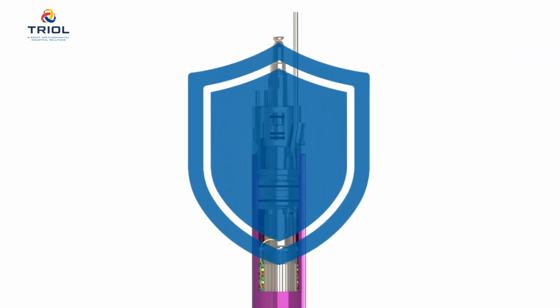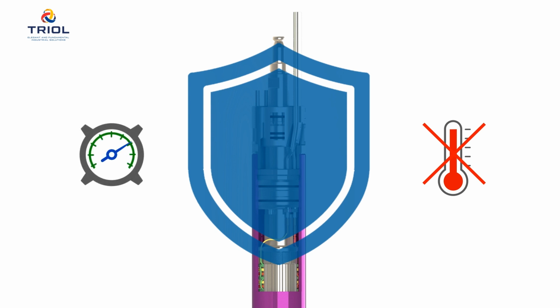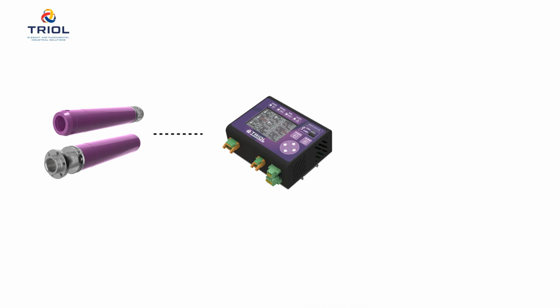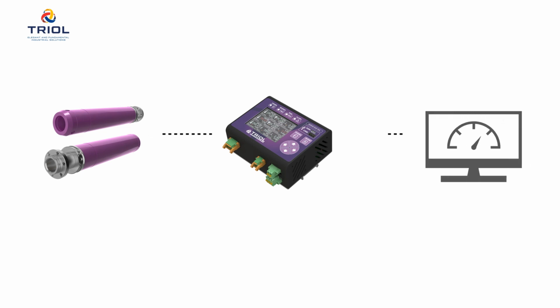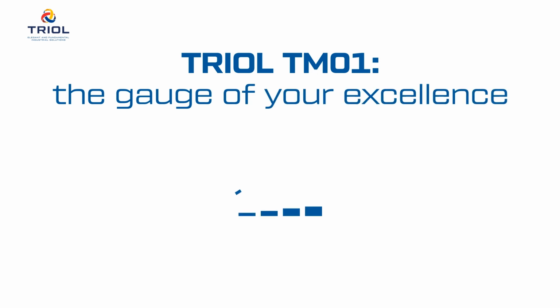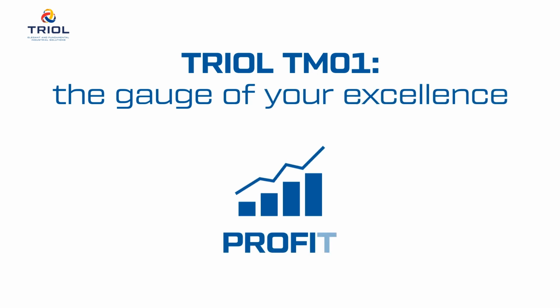Helps to protect the motor and power cable from overheating. Prevents pump stalling due to low dynamic level. Reduces the percentage of equipment failures. Optimizes the operation of the electric submersible pump installation. Thanks to effective algorithms for requesting the status of sensors and data management systems, Triol TM01-10 provides continuous monitoring of the equipment status and allows timely decisions to be made to optimize the performance of the monitored equipment. We are confident that Triol TM01-10 will allow you to maximize well production.